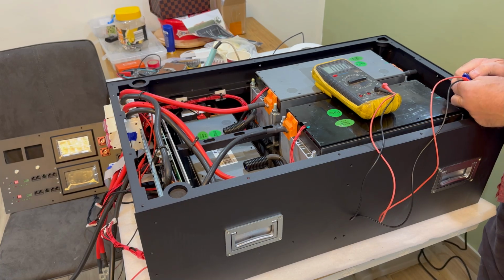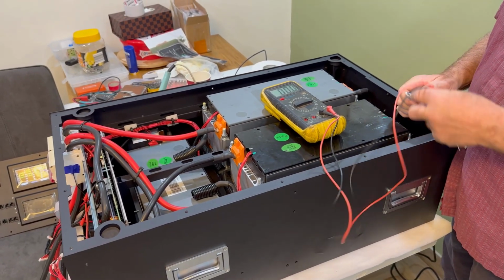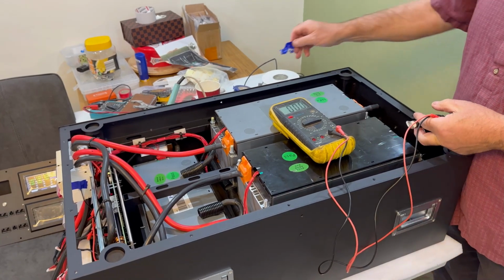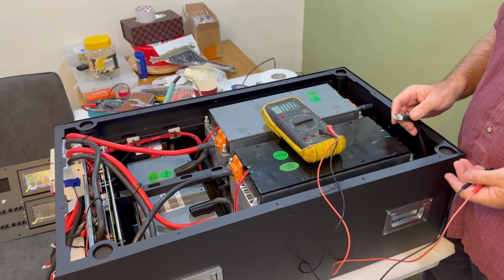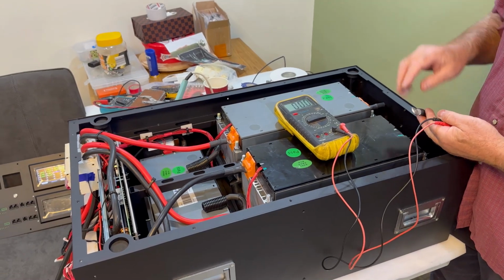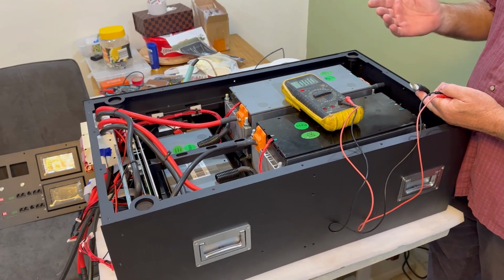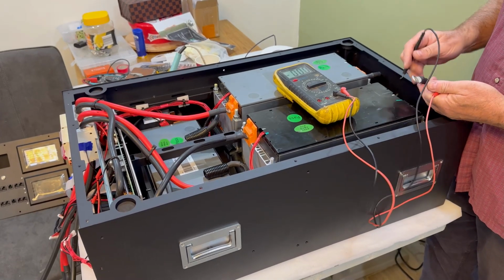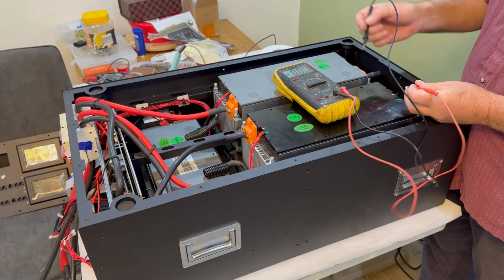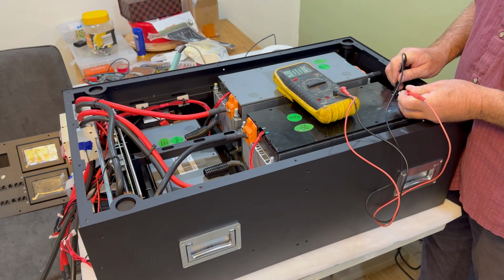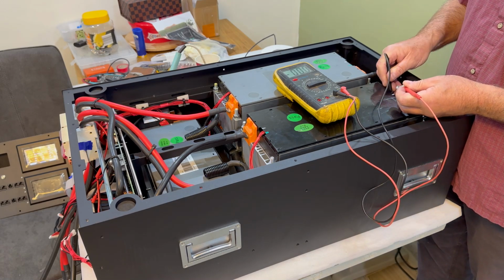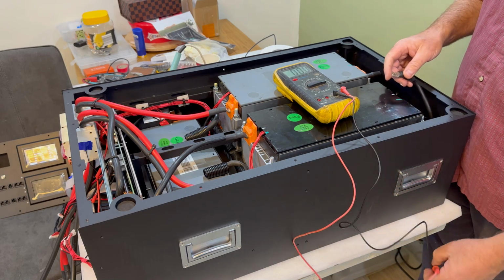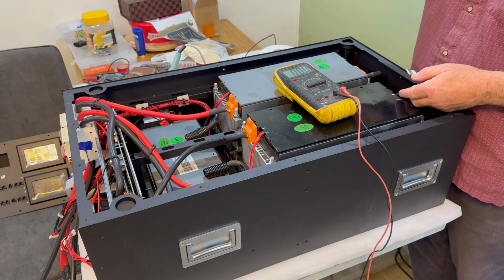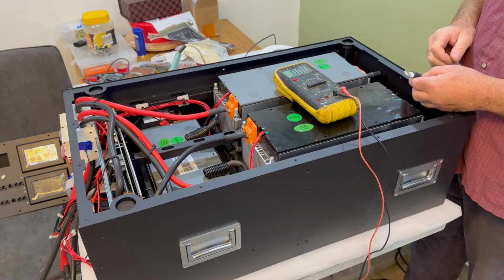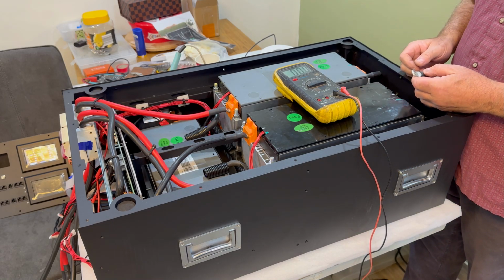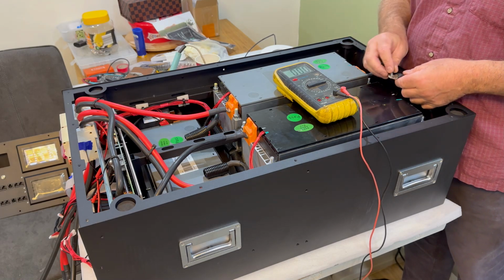We're on DC volts. Good practice is, before you make connections, you check the voltage between the connections you expect. As there should be nothing switched on at that end, when I make this connection there shouldn't be any current flow, so I'm expecting 0 volts. We'll see what we get, and we get 0 volts on the meter. So now I'm confident I can put that connection together without any nasty sparks. If all of a sudden I got 20 or 30 volts, I'd be concerned, since I'm expecting 0, and that would make you investigate before you throw the connection together.